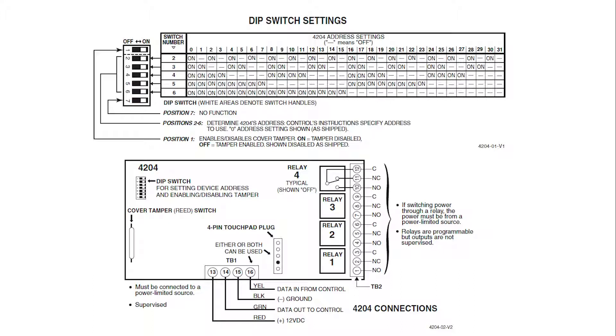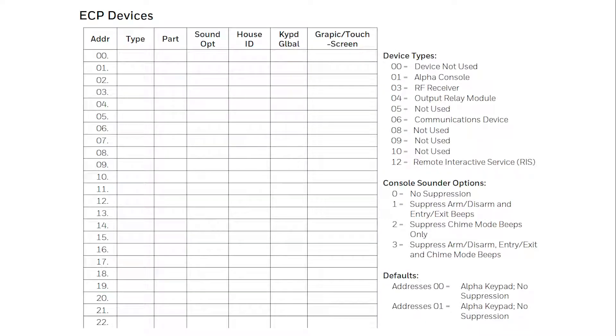Now that we know how to address and wire a relay, we can begin programming. Once in panel programming, enter Field 93. This is a menu mode. All selections have their own submenu and have a corresponding worksheet in the panel's programming guide. The first question will ask zone programming, yes or no? Press 0 for no until you reach device programming.